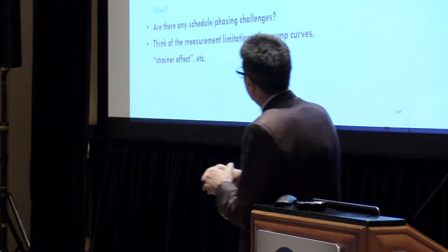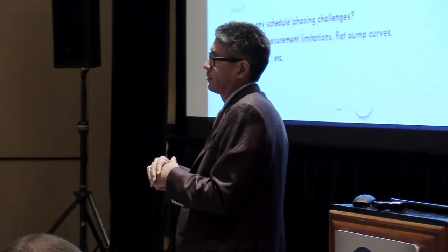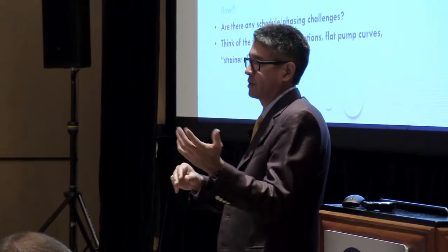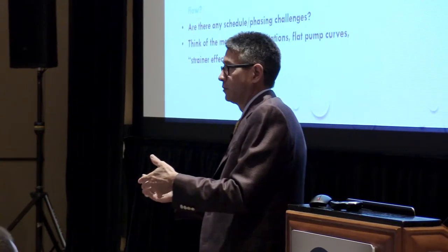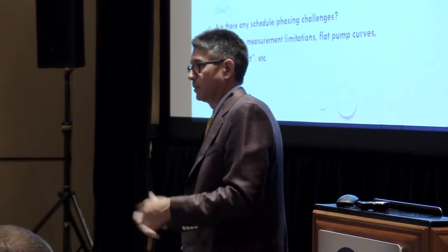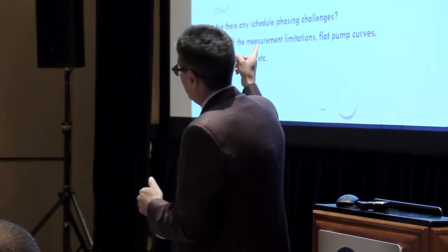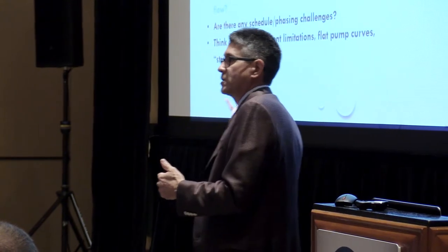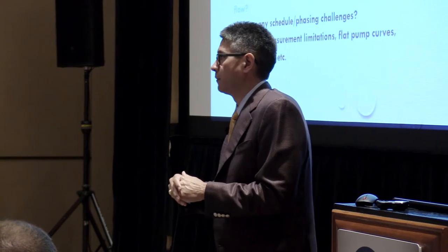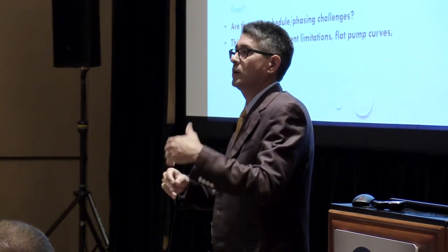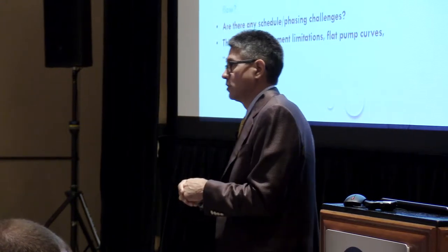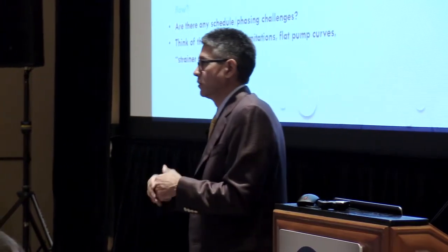Start looking at that. Like I said, if you have excess flow, look at automatic flow limiting devices. You notice how the industry over the past 5 years changed the name from automatic balancing valves to automatic flow limiting devices, because they don't automatically balance. We were kind of hoping they did, but they didn't. They limit flow. That's the main gist of that automatic flow limiting device. So it prevents overflow in situations that can create your delta T problems and that kind of thing. So you might have a great application where you can use those and they'll help out and they'll be an efficient solution for that side.